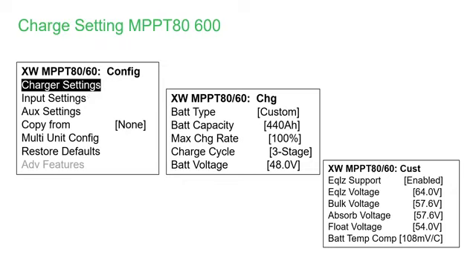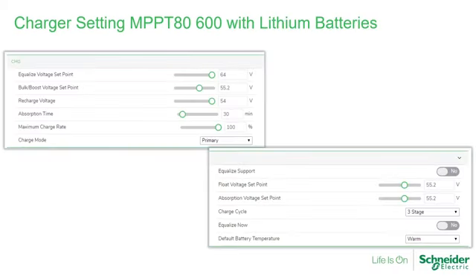The next recommendation is always select the battery type custom. Although when you look at the menu, you're going to find some presets, flooded, AGM, and gel, presets from the factory. And if you select them, you can't make any changes. This is why I recommend you always use custom. Once you select custom, then all of this menu becomes available to you, and now you can actually program each one of these settings exactly as the battery manufacturer is recommending. Next one is using the gateway. And although the screen looks a little bit different than the menu structure of the system control panel, the settings are exactly the same settings, right? So we're going to actually program exactly the same settings. And again, I recommend that you always select custom.